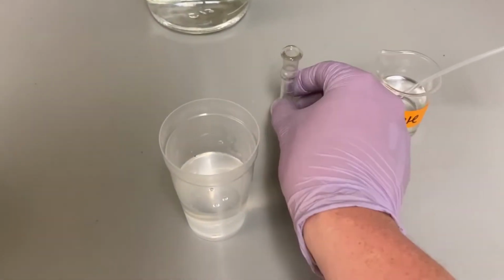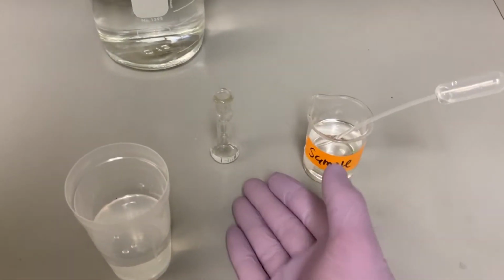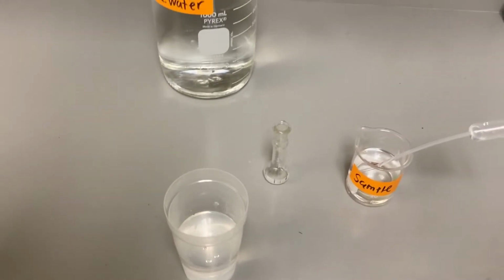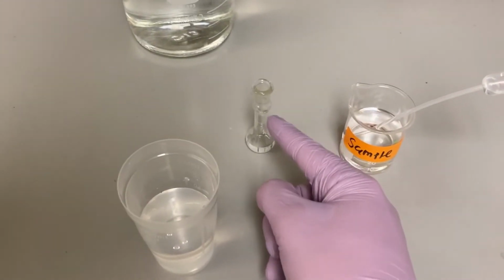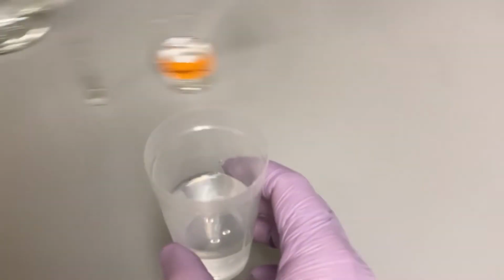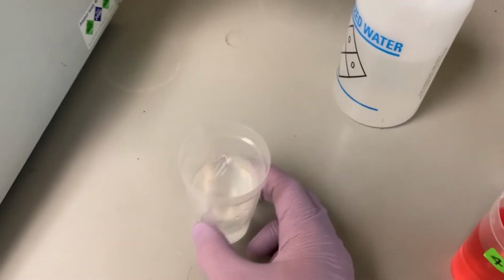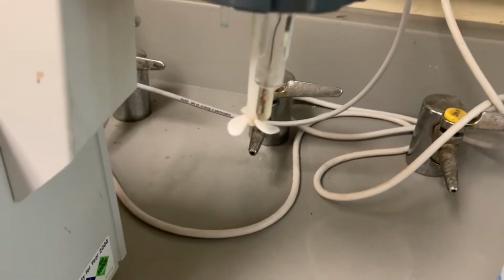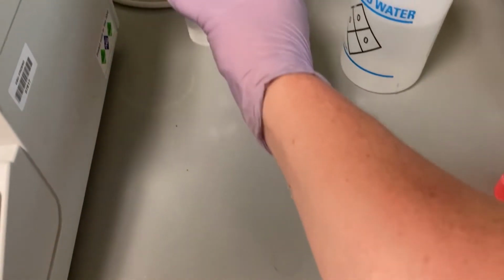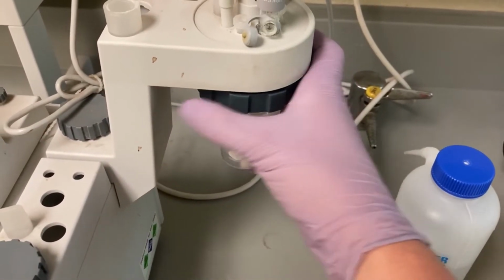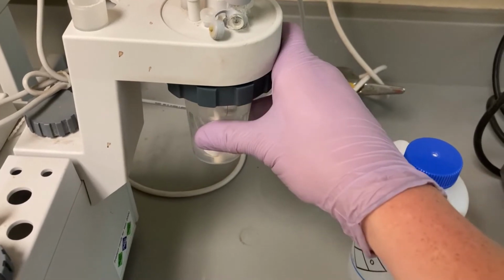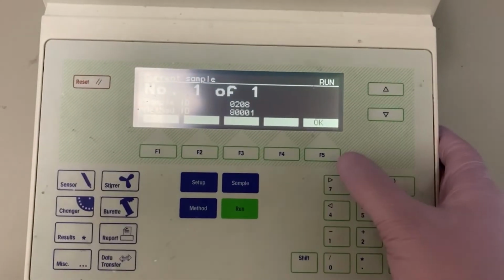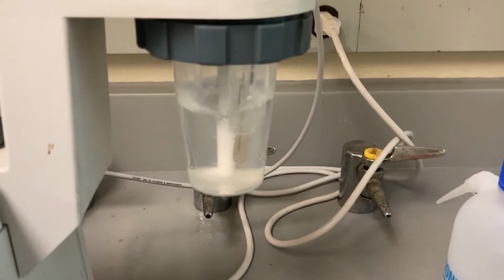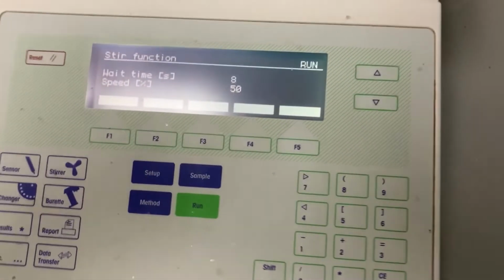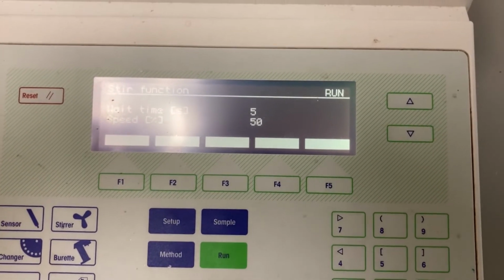And if you're doing many samples, it's nice to have two 25-milliliter volumetric flasks and many pipettes. So you can wash one of these and have it drying while you use the other. And you don't need to mix it because the propeller on the auto sampler will do that for you. So you just insert the sample, tighten the gray nut, and from the screen you hit OK. And it will start to mix the sample for you. It will do this for 5 seconds, and then it will start the titration.